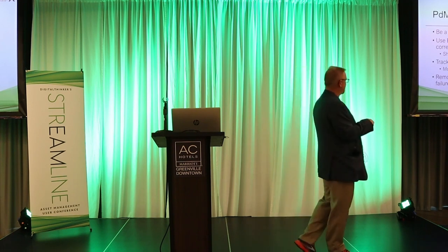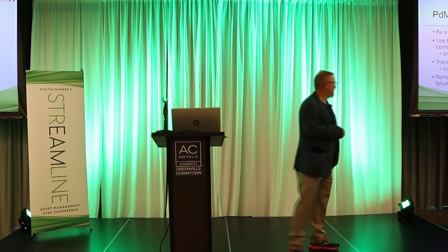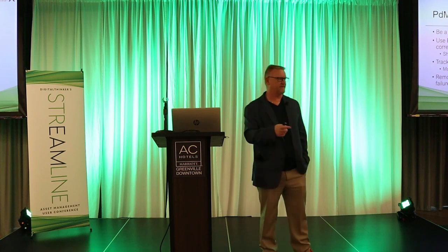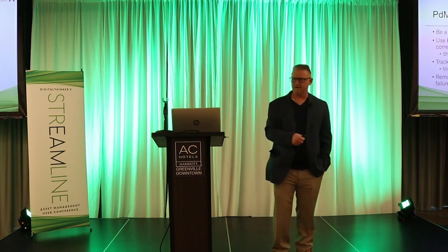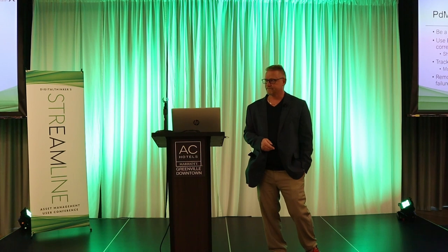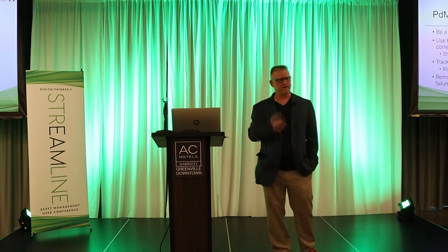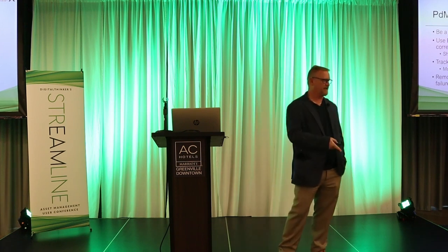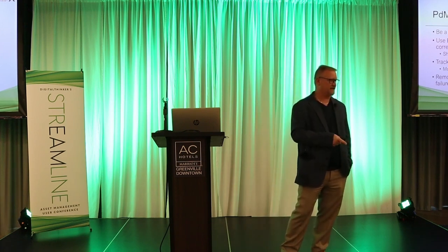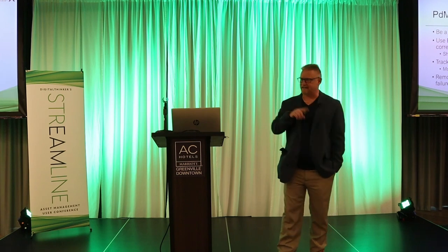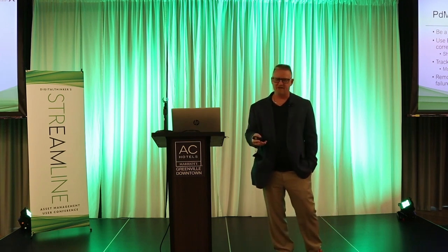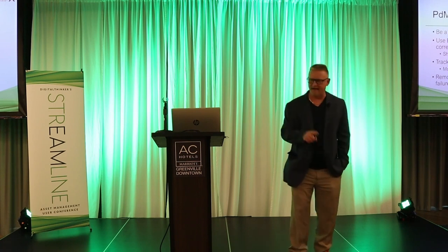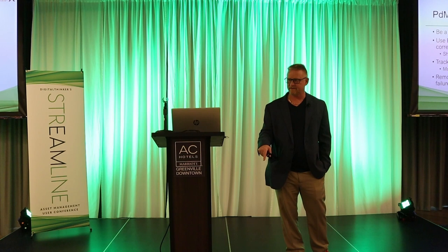Track your cost savings and avoidance. Make sure everything goes inside EAM. All of your collections should be documented in the EAM, and all of the output from the report to go do the work that's repair should also be in EAM. The other thing that you have to do is remove all of the physical intervention tasks from your PM tasks and your task lists that are addressing the same failure mode. If I'm using vibration analysis on my pumps, I know whether or not I'm going to have a coupling failure. I should not have a physical intervention to inspect the couplings.